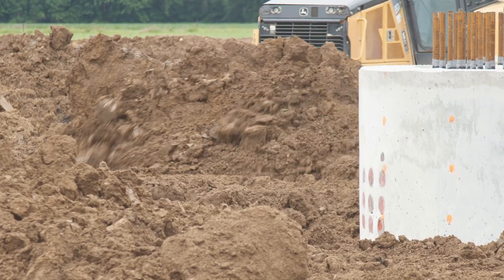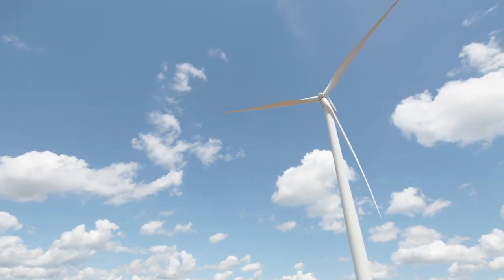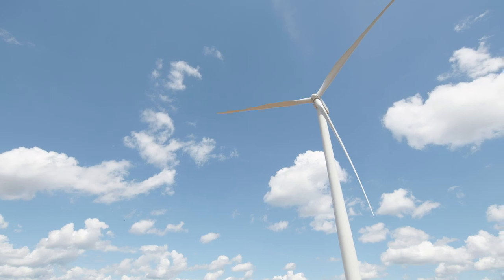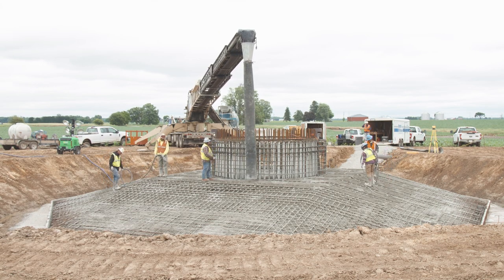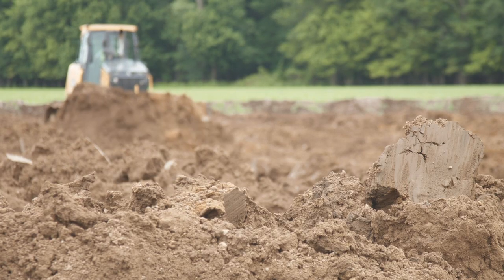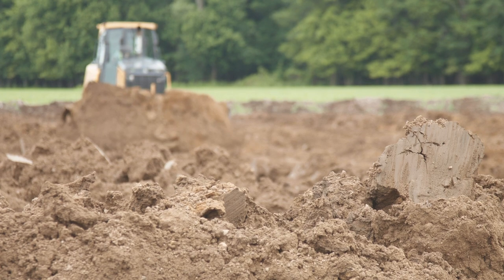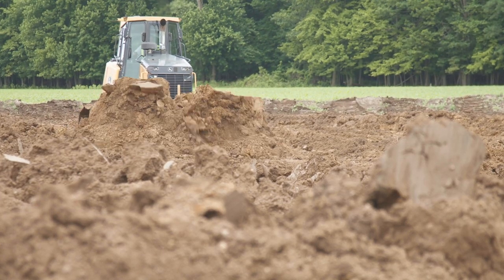One interesting thing is these towers are quite large and the wind hits them. They have what's called a tipping moment, so part of keeping this structure standing is the really large, heavy concrete foundation and all the steel in it, in conjunction with the material put back over that spread footing. That's part of the calculation that keeps this thing standing up.